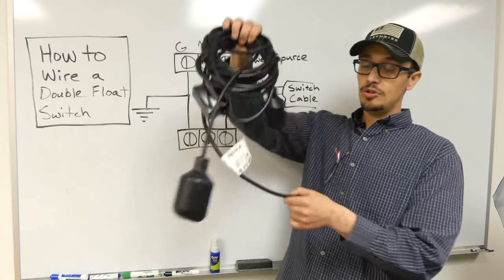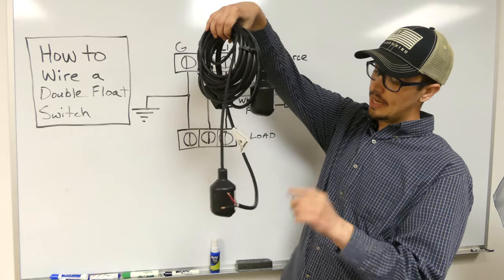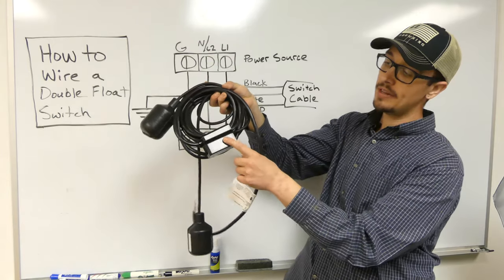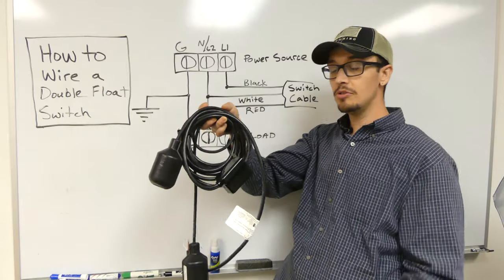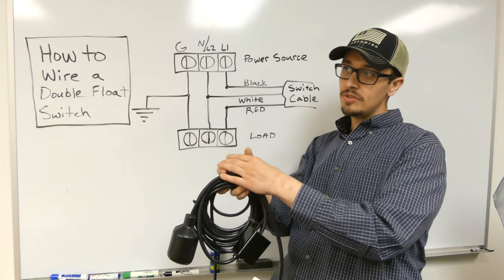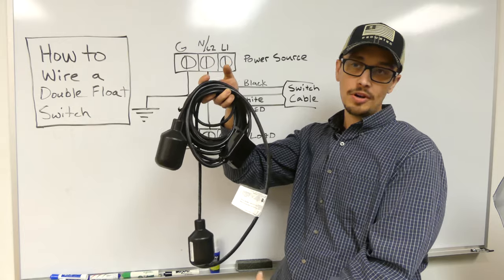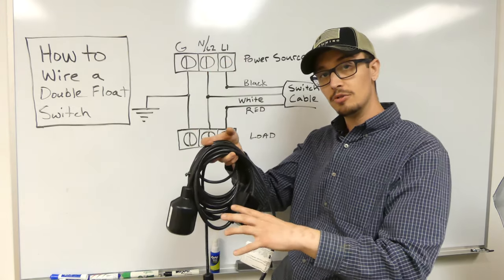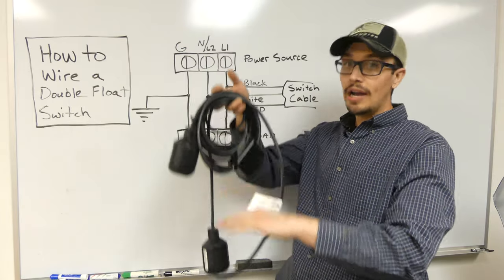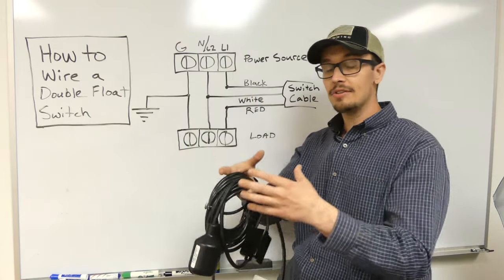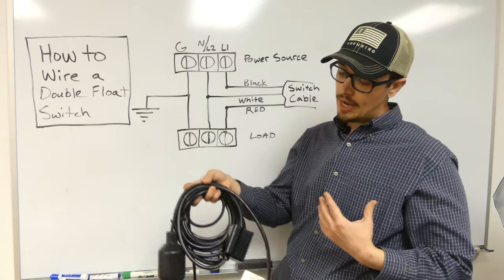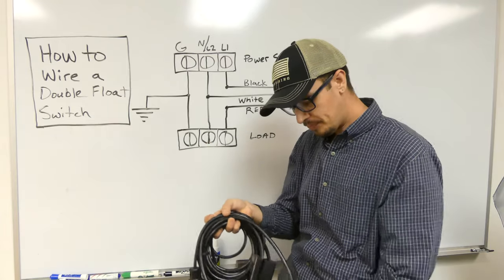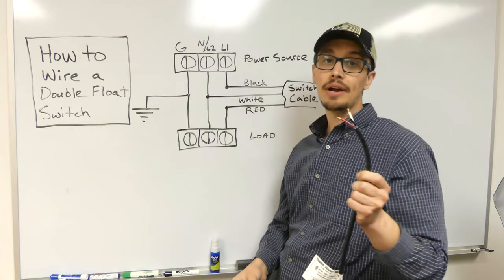So if you're not familiar with a double float switch, we essentially have two floats in here and this one is labeled the bottom, this one is labeled the top. We've got a relay here. So what we're able to do is in relatively deep applications where you maybe don't have a lot of room for a wide angle swing, you can use the double float switch for a wider range of pumping in those tighter diameter applications. And it's also intended for direct pump control.